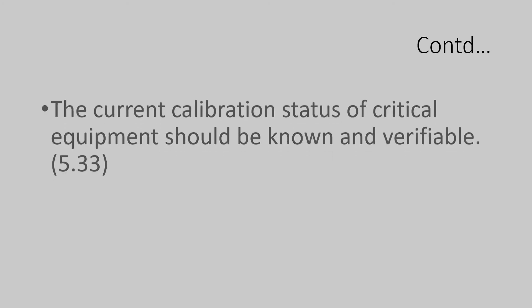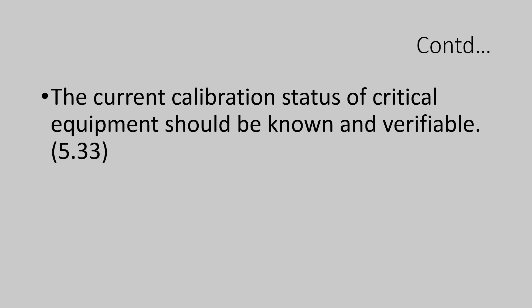Let us see what section 5.33 says: the current calibration status of critical equipment should be known and verifiable. There should be a clear label affixed on the equipment with the details of date of calibration, next calibration date, and the person who carried out the calibration.